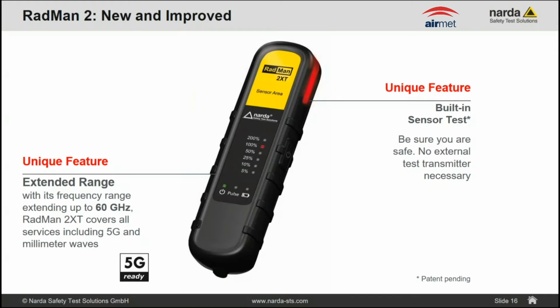So when you switch on the instrument, it will check that all the 6 connections to these 6 antennas are low ohmic. If they are high ohmic and open, then there will be an alarm and the instrument will not work. The other instance may happen that you carry or expose the instrument to excessive radiation.